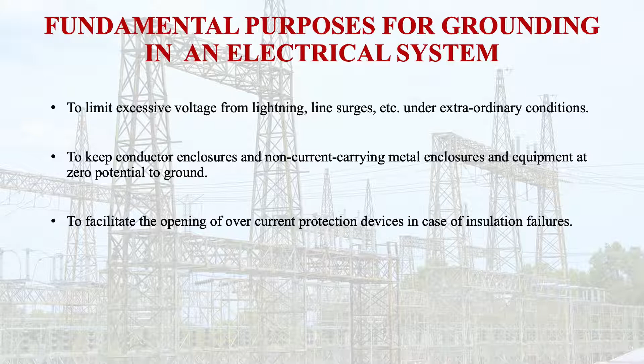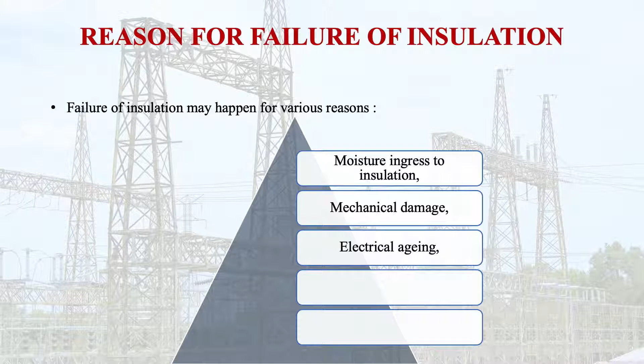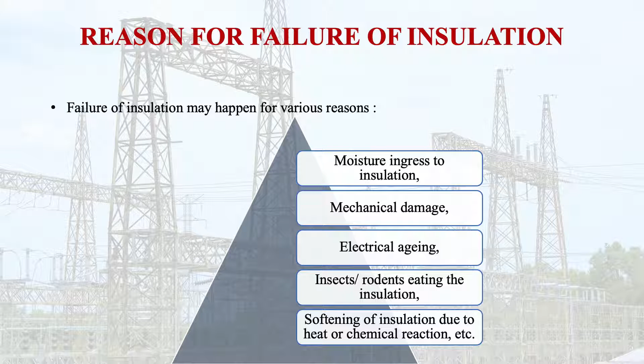Suppose there is an insulation failure where a non-current carrying metal enclosure is present, and because of the failure in the insulation over the conductor, current may leak to that enclosure. In that case, we want the protection devices to operate, so grounding may facilitate the opening of overcurrent protection devices. Failure of insulation may happen for various reasons, like moisture ingress to insulation, mechanical damage, electrical aging, or insects eating the insulation. Then there is softening of insulation due to heat or chemical reaction. So there are various reasons which may cause the failure of insulation.